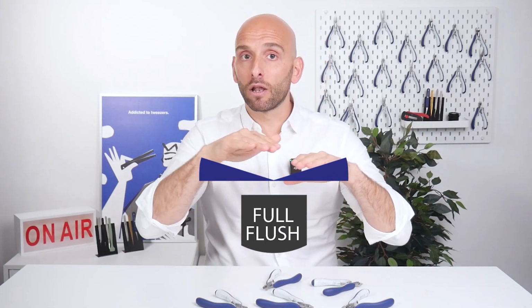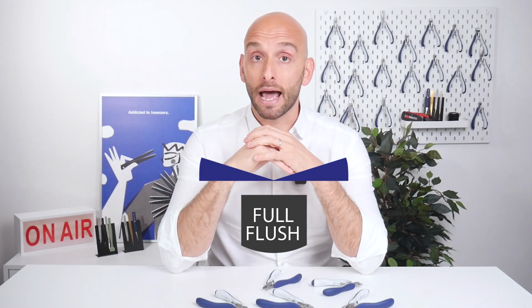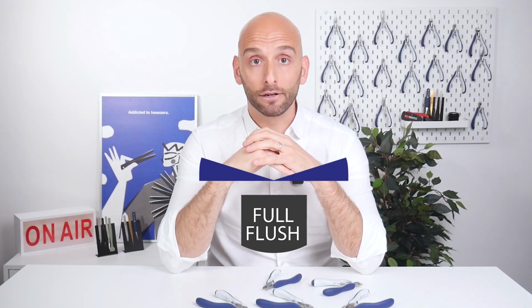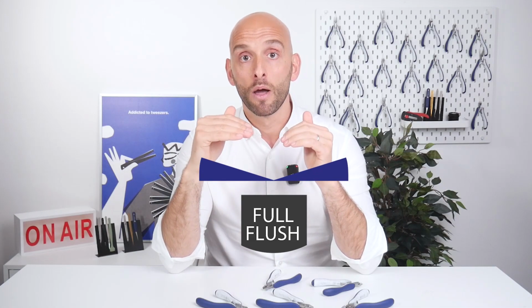And the third is the full flush. No bevel on either cutting edge. The backside is absolutely flat. Under magnification you can see a line on the lead where the edges come together, but you will not see a pinch. This is the most common finish in the medical device field. However, being an extreme cut, the tool life of a full flush wire cutter is significantly shorter.